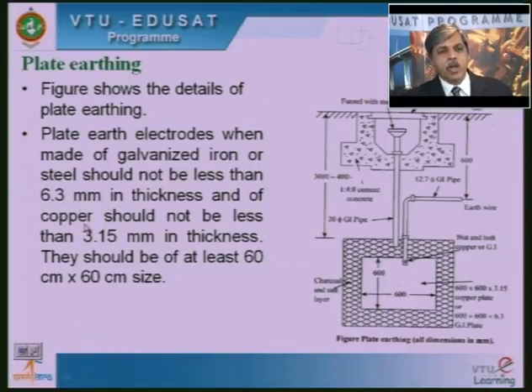6.3 is almost double, no? 3.15 and 6.3, this is double. So the weight also increases, but it is much cheaper compared to the copper plate. Therefore, normally we use galvanized iron or steel sheet for plate earthing. Because I am using plates, I call this type of earthing plate earthing.